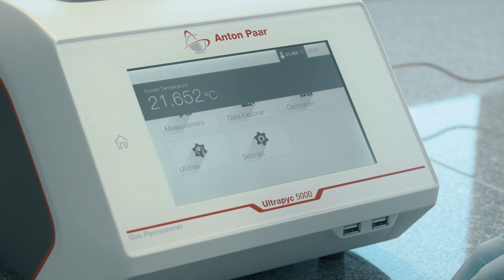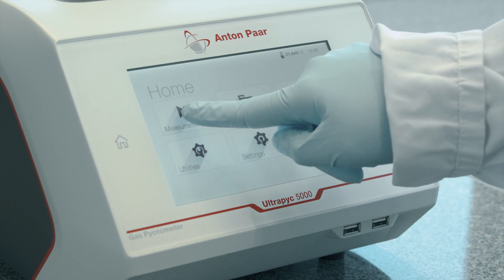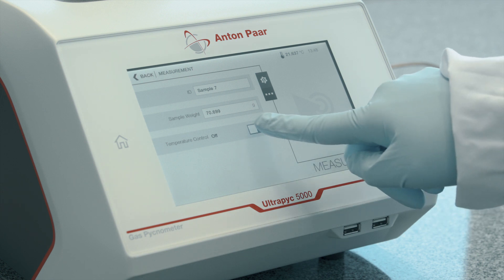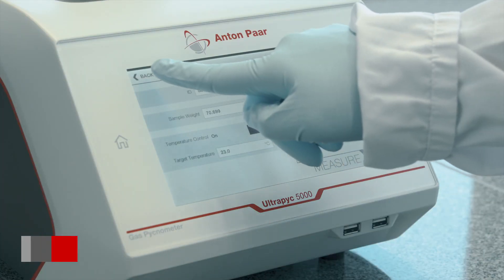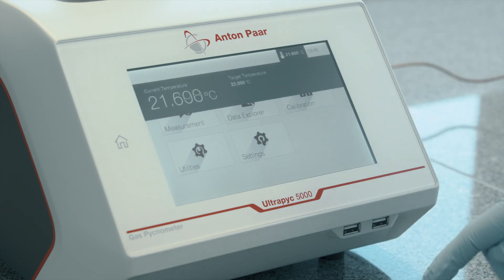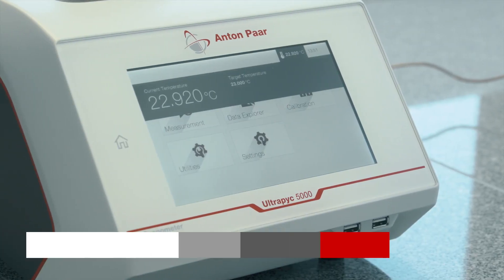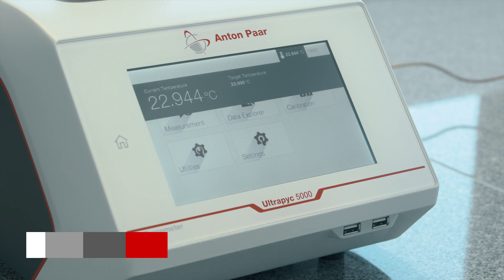Another component of highly accurate gas pycnometer readings is a stable temperature throughout the entire process. The Ultrapyc 5000 instruments are equipped with Peltier control and therefore able to maintain temperatures from 15 to 50 degrees Celsius at a stability of plus or minus 0.05 degrees. This eliminates the need for external temperature control baths and saves you money and valuable bench space.